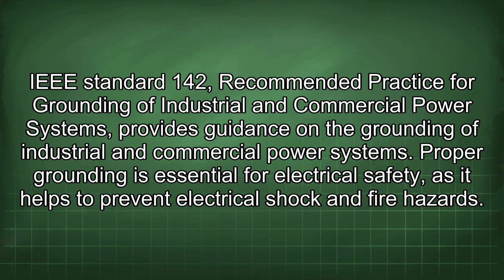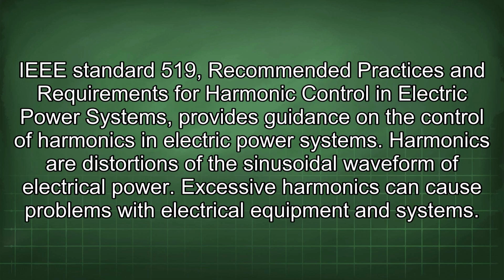IEEE Standard 142, Recommended Practice for Grounding of Industrial and Commercial Power Systems, provides guidance on the grounding of industrial and commercial power systems. Proper grounding is essential for electrical safety as it helps to prevent electrical shock and fire hazards. IEEE Standard 519, Recommended Practices and Requirements for Harmonic Control in Electric Power Systems, provides guidance on the control of harmonics in electric power systems. Harmonics are distortions of the sinusoidal waveform of electrical power. Excessive harmonics can cause problems with electrical equipment and systems.